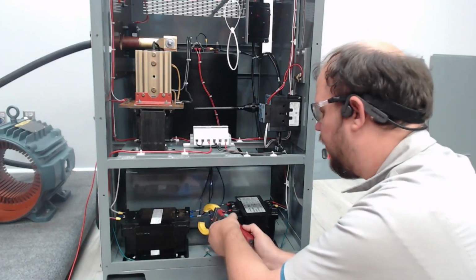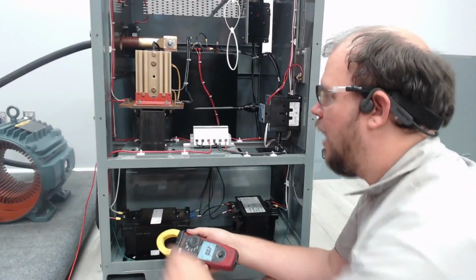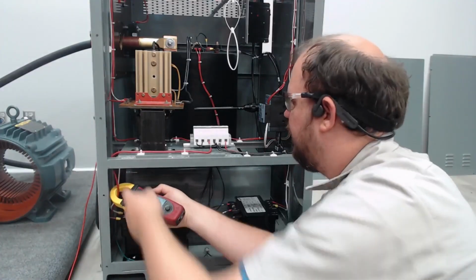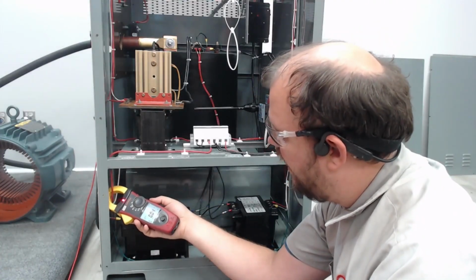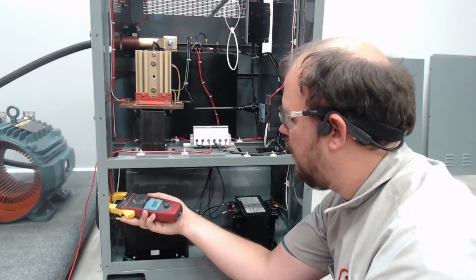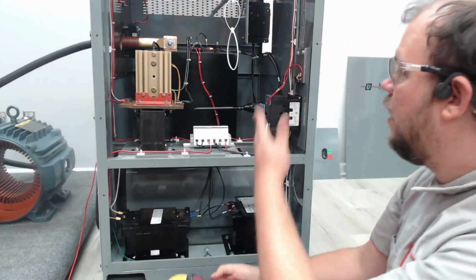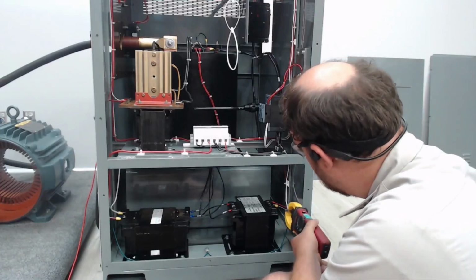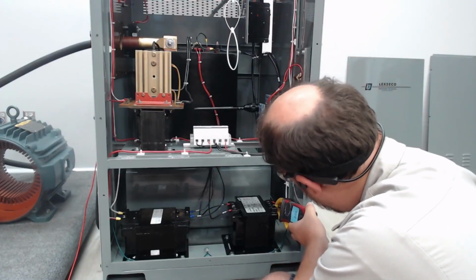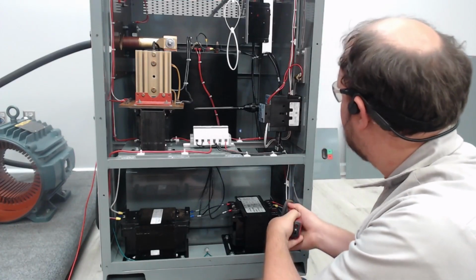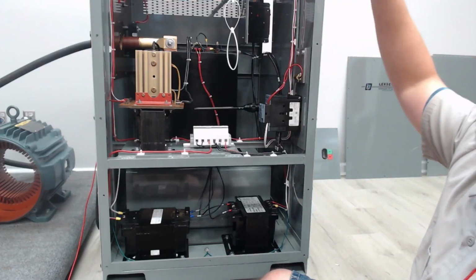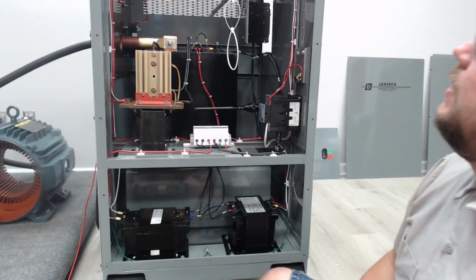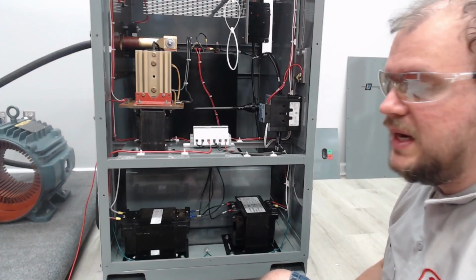No issues there. We're going to check the outgoing as well because it'll have a little higher fusing, 0.05, so it's got even less of a draw because there's nothing on pulling it. I'll check this one too. This one should be about, yeah, 0.06. Once again, there's just no draw going on. We don't have laptops or printers hooked up for this rental unit, but even if you did, they would be nominal at best.